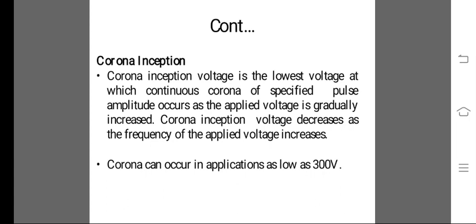Corona Inception. Corona Inception voltage is the lowest voltage at which continuous corona of specified pulse amplitude occurs. As the applied voltage is gradually increased, Corona Inception voltage decreases as the frequency of the applied voltage increases. Corona can occur in applications as low as 300 volts.